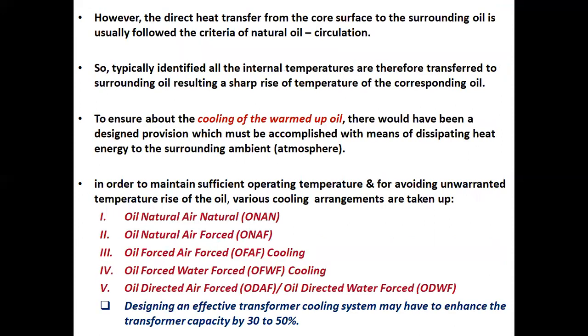The core heat value and its dissipation depend on the grade of iron and its flux density. However, the direct heat transfer from the core surface to the surrounding oil usually follows the criteria of natural oil circulation. So, typically, all the internal temperatures are transferred to the surrounding oil, resulting in a sharp rise of temperature of the oil. To ensure cooling of the warmed up oil, there must be a design provision for dissipating heat energy to the surrounding ambient or atmosphere.